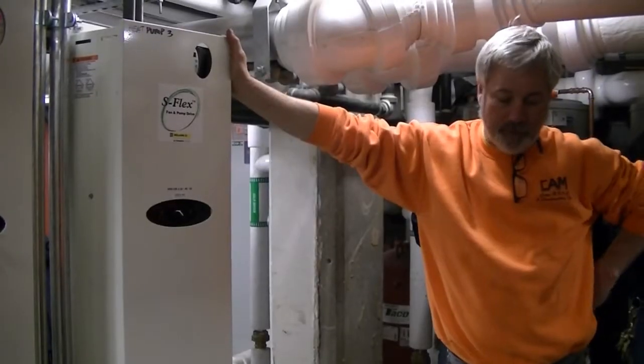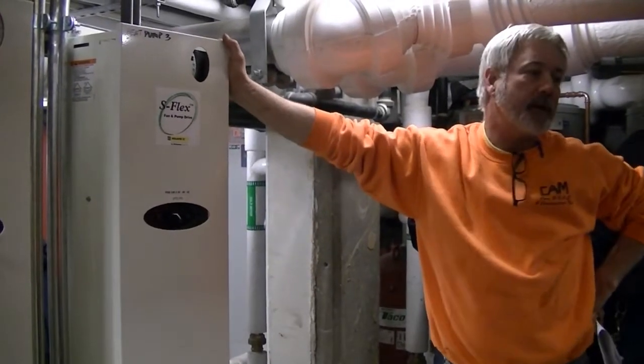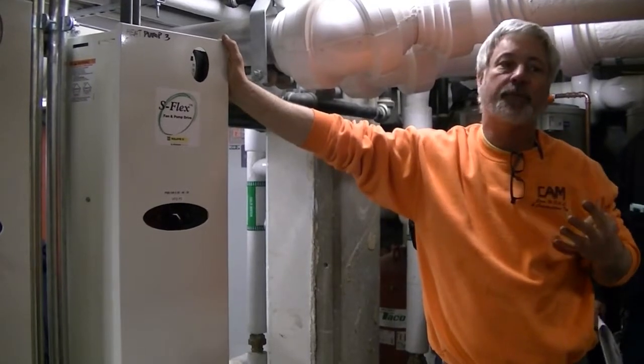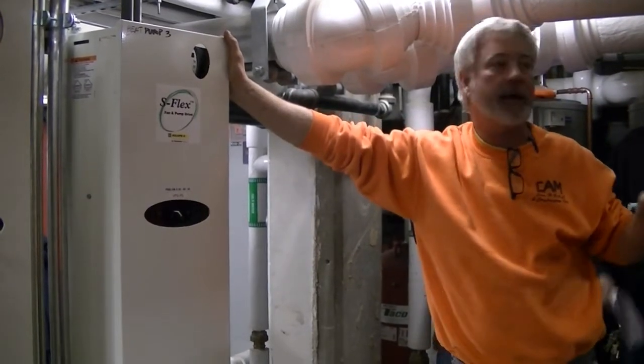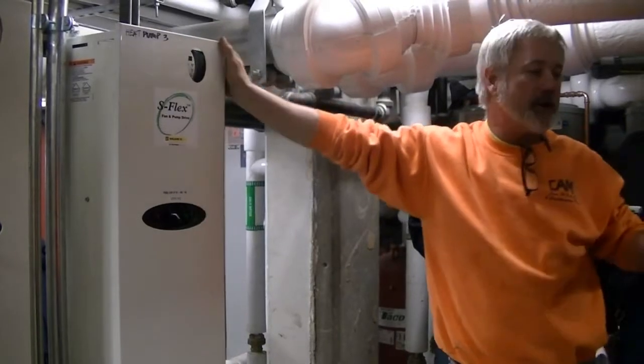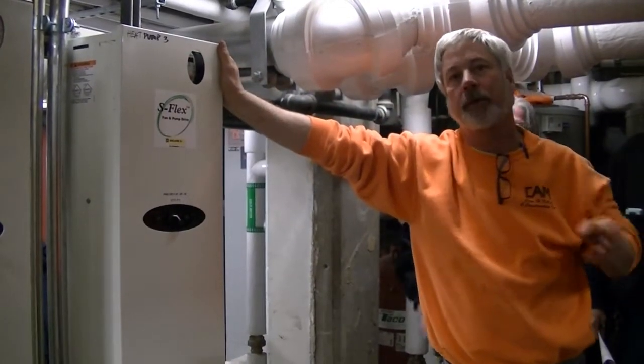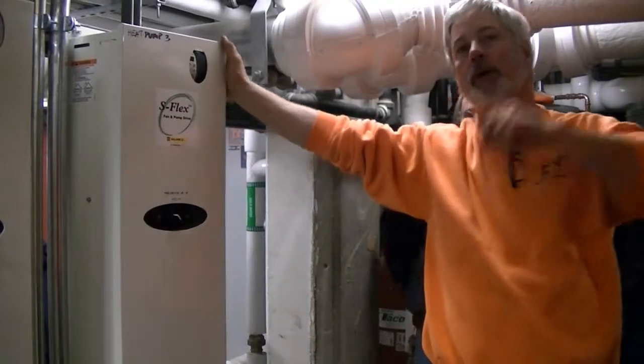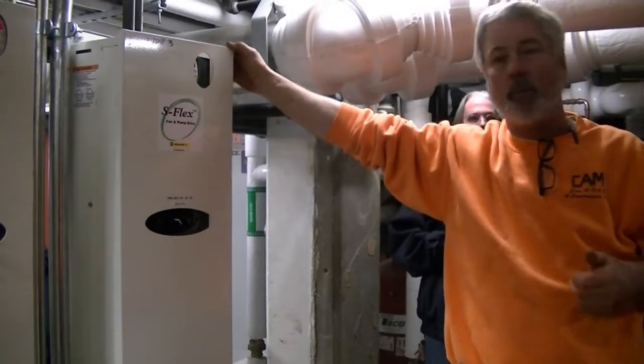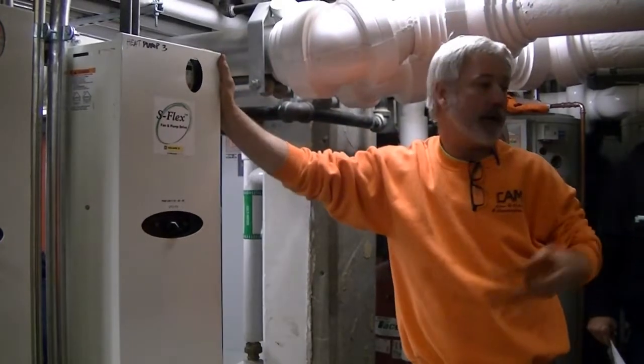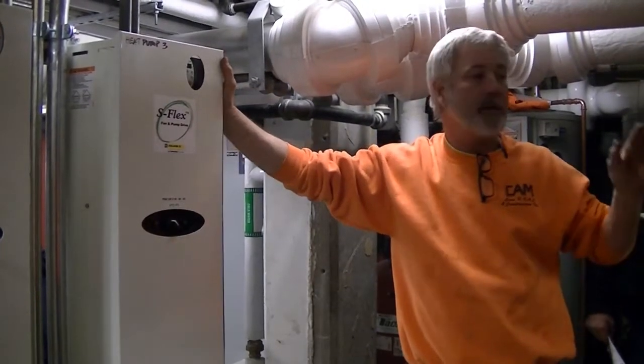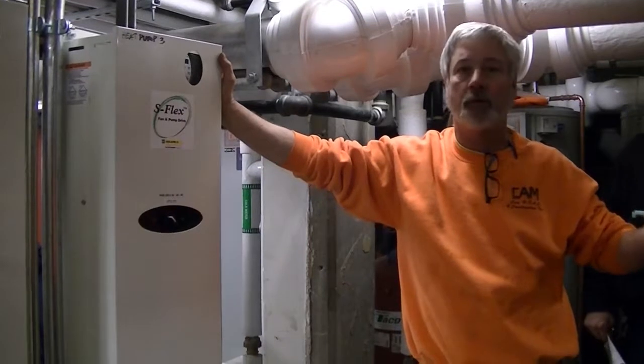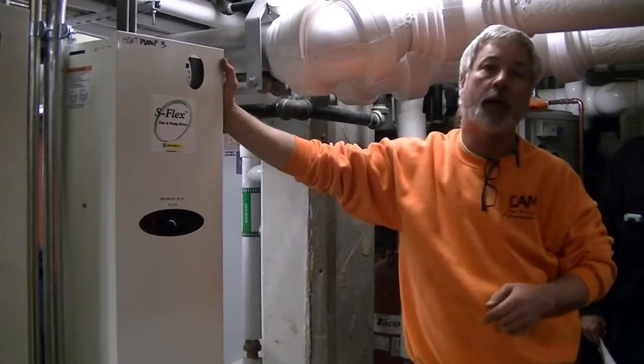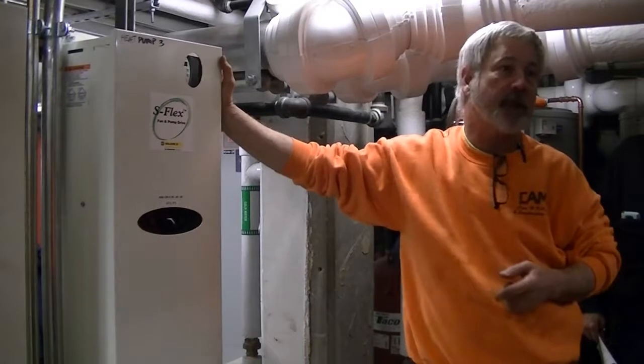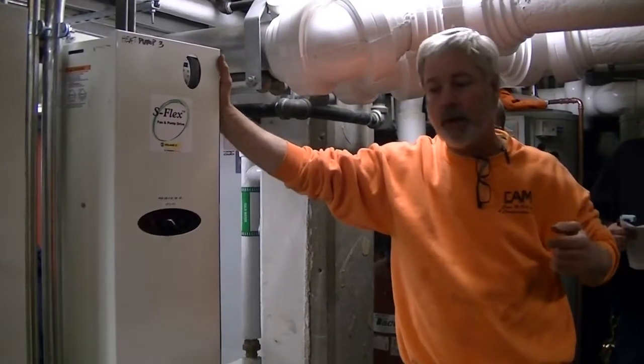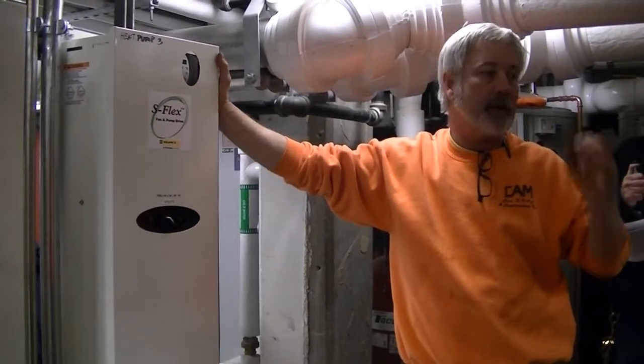A brief overview on the design of the system. You have 4 boilers and you have a generator, or a cogen. The cogen is considered boiler plant number 1, and then your boilers kick in 2, 3, 4, and 5. The boilers are marked 1 through 4. The cogen is marked CG1. Don't get confused, because the cogen is actually boiler number 1 when we get to the control layout on the Viessmann cascade controller.